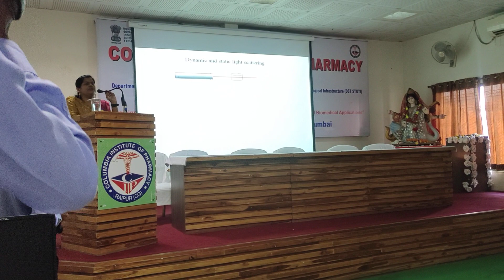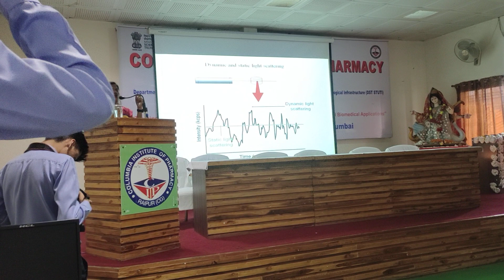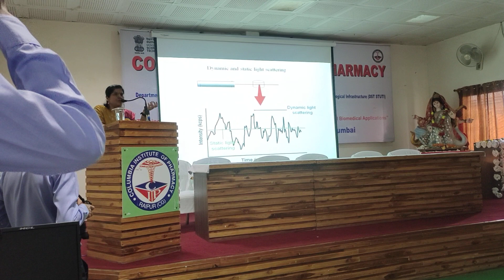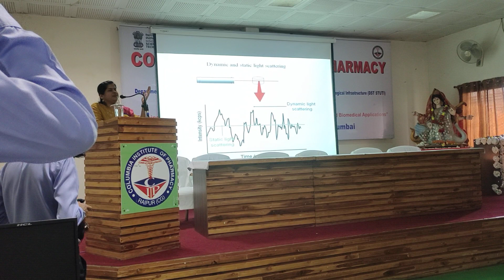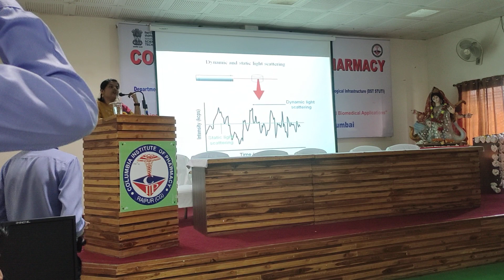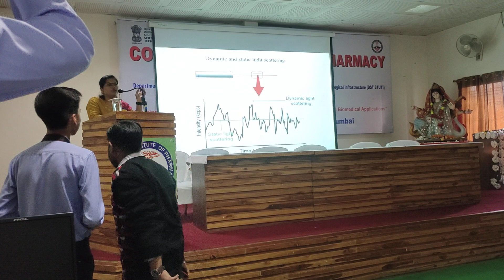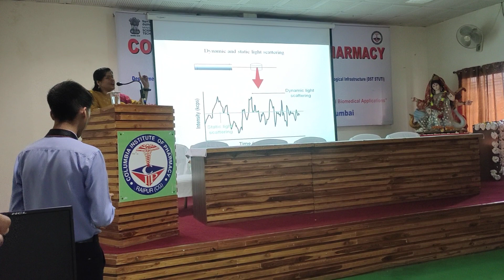Now, this is the slide which shows the difference between dynamic and static light. In the diagram, we have run our sample in the machine. After running the sample, if we get a straight line, it means our particles have no impact on the light through which they are scattered, and that will be called static light. But if we have prepared the sample correctly and it has a number of particles, and we have placed our cuvette in a suitable position, when the light passes we will get a zigzag graph, which is called dynamic light scattering, and after the equilibrium only we will get the result. So the basic principle is dynamic light scattering, and the graph is plotted between intensity of light and the time taken to achieve the equilibrium.